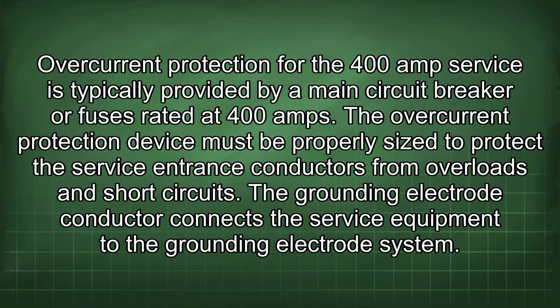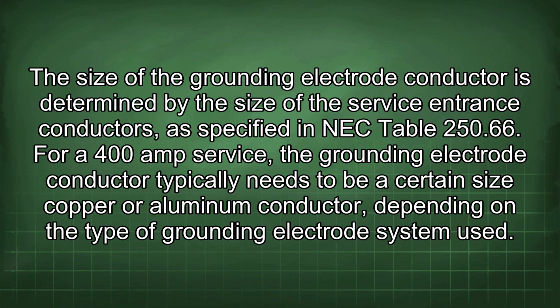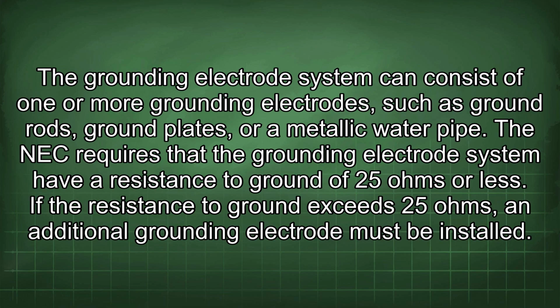short circuits. The grounding electrode conductor connects the service equipment to the grounding electrode system. The size of the grounding electrode conductor is determined by the size of the service entrance conductors, as specified in NEC Table 250.66. For a 400 amp service, the grounding electrode conductor typically needs to be a certain size copper or aluminum conductor, depending on the type of grounding electrode system used. The grounding electrode system can consist of one or more grounding electrodes, such as ground rods, ground plates, or a metallic water pipe. The NEC requires that the grounding electrode system have a resistance to ground of 25 ohms or less. If the resistance to ground exceeds 25 ohms, an additional grounding electrode must be installed.